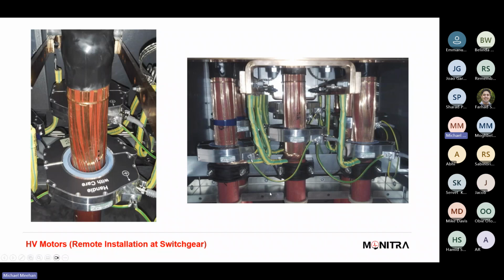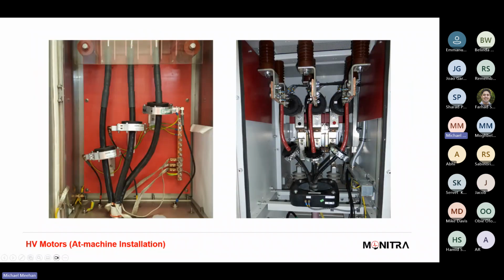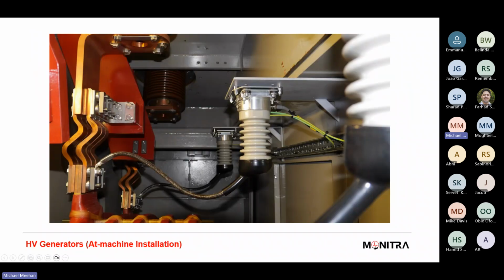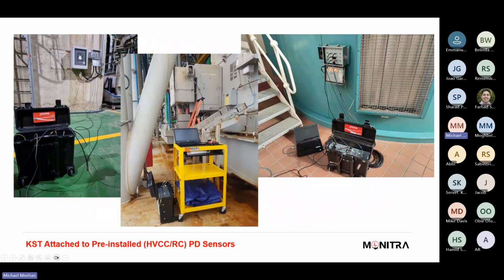So when you're thinking of installing these coupling capacitors or HFCTs, some of the limitations might be if you're doing it after the fact, after it's been in operation for a while, you do have limitations in cable box sizes, potential limitations with cable access, cable screen configuration. So these are examples of perfect configurations, I guess, in terms of we're able to install these after the fact and give the client the condition monitoring that they require. The typical HFCT, HVCC high voltage coupling capacitor install. We use bespoke brackets, and then you've got the direct measurement from the machine itself.